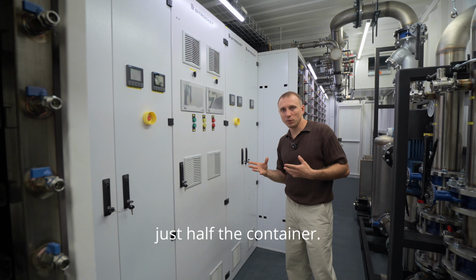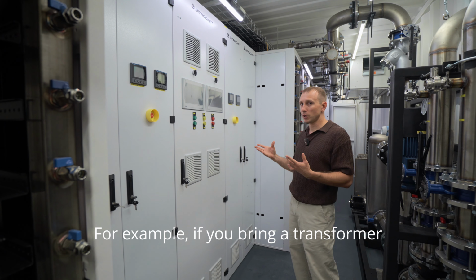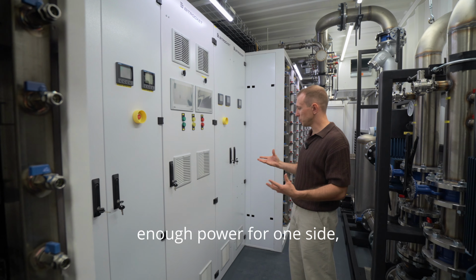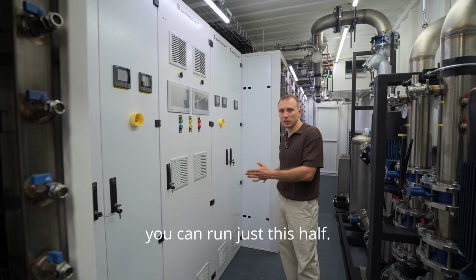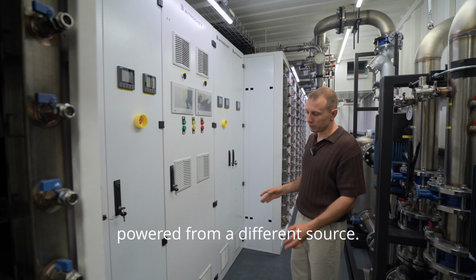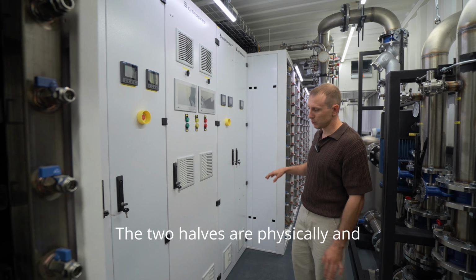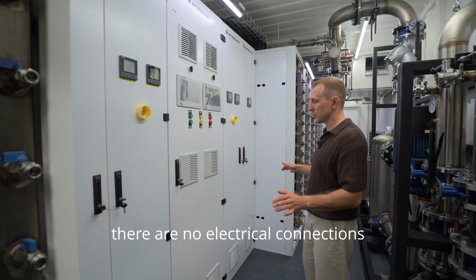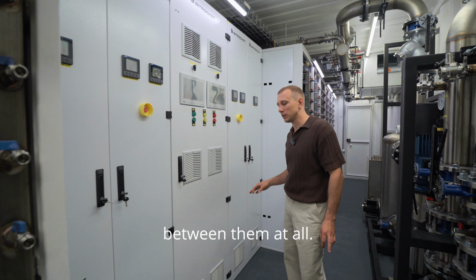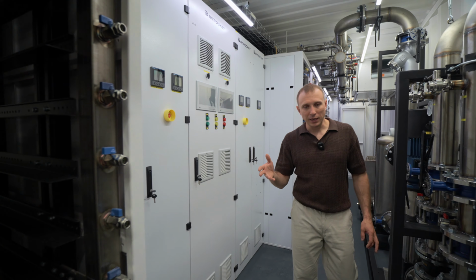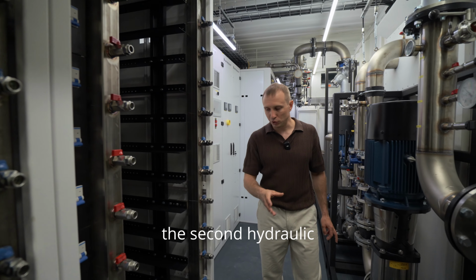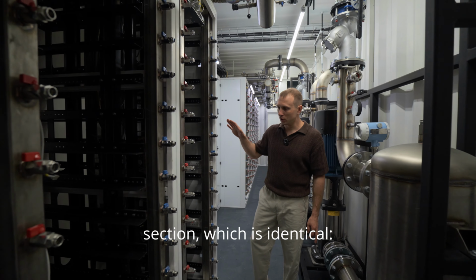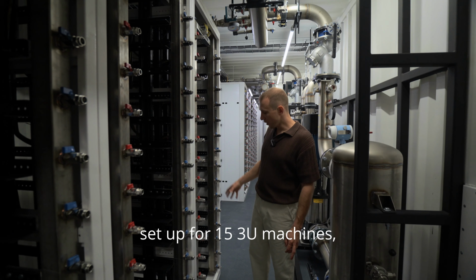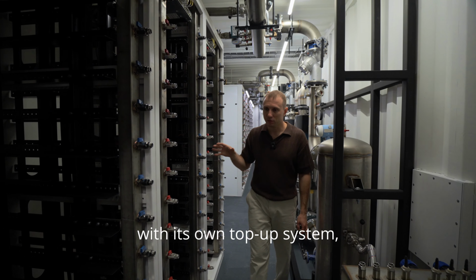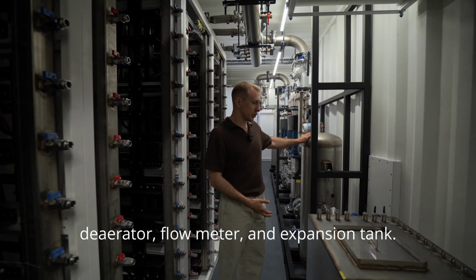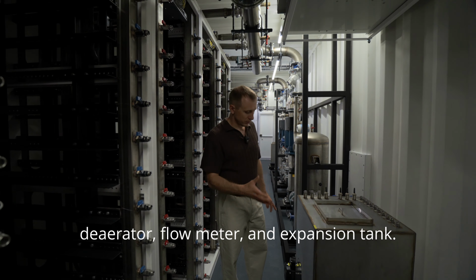You can even power just half the container. For example, if you bring a transformer station and only have enough power for one side, you can run just this half. The other half can later be powered from a different source. The 2 halves are physically and galvanically isolated. There are no electrical connections between them at all. If we move further down, we'll see the second hydraulic section, which is identical, set up for 15 3U machines, with its own top-up system, deaerator, flow meter, and expansion tank.